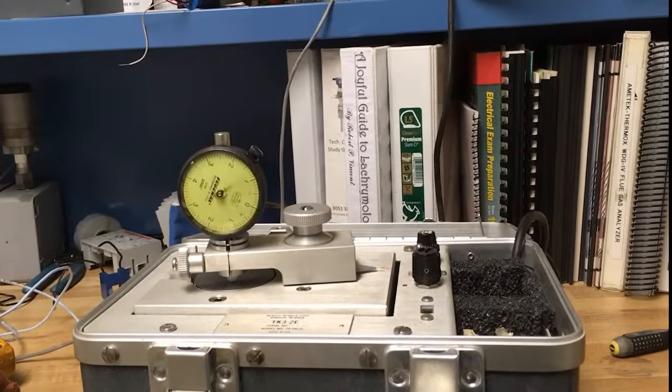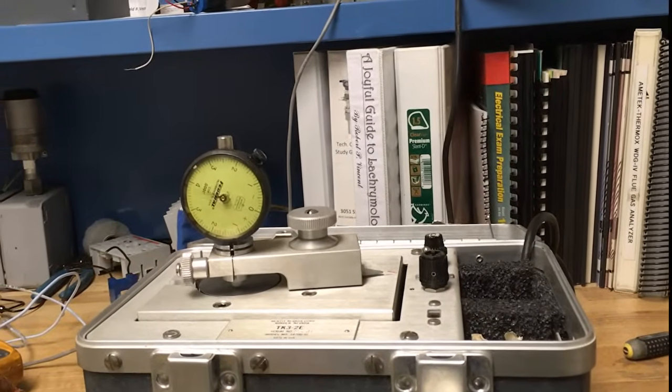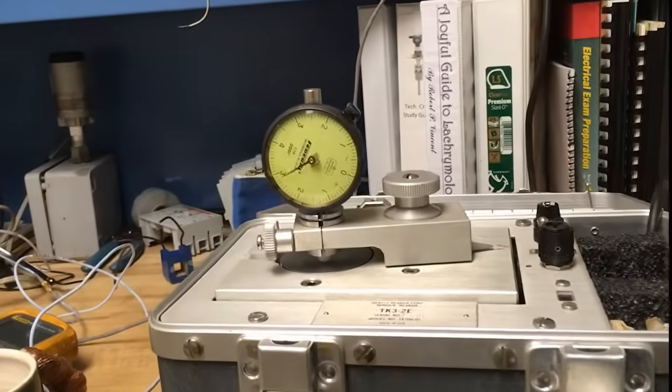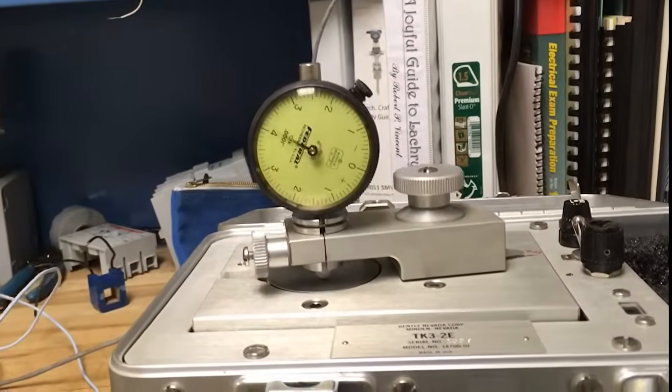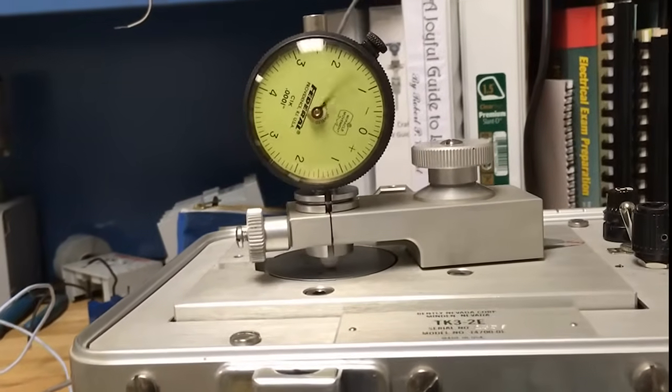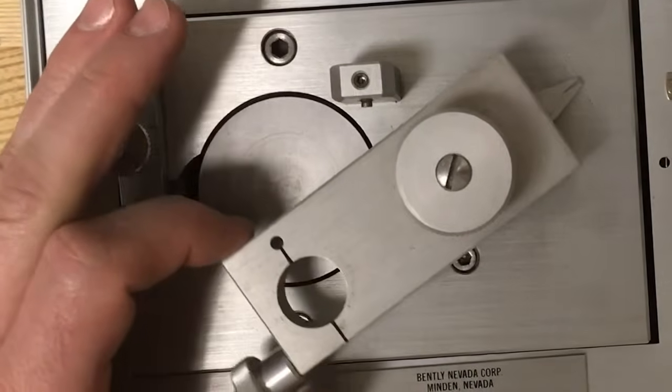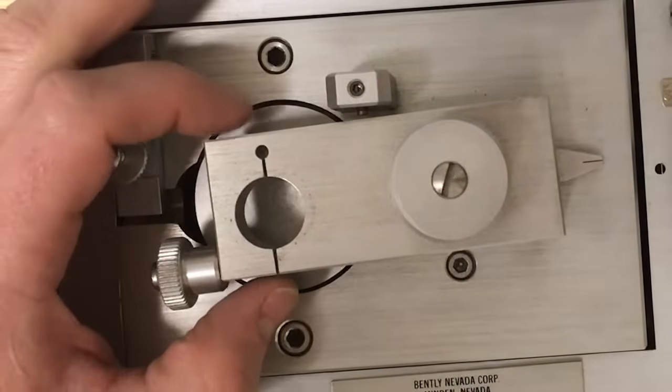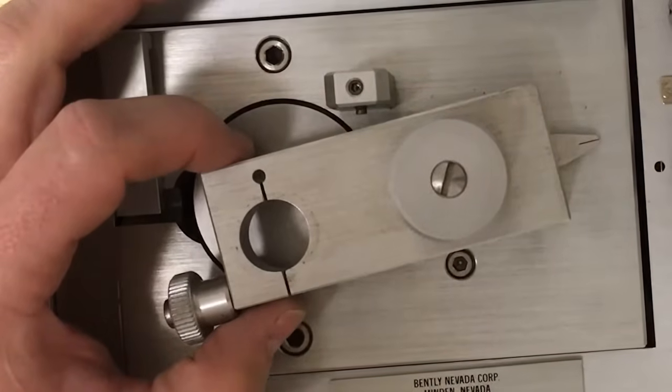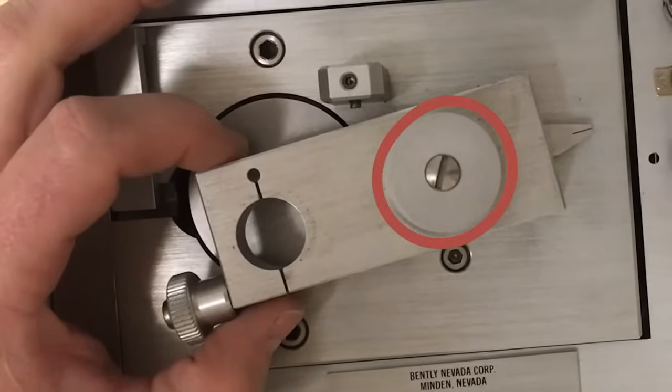The process begins by setting up the test device. If your unit has a reference mark for the desired amplitude of oscillation, place it on 5 mils. If there is no indication, hold the receiver over the center of the disc, then rotate approximately half the distance to the edge of the disc. Secure the swing arm in place.